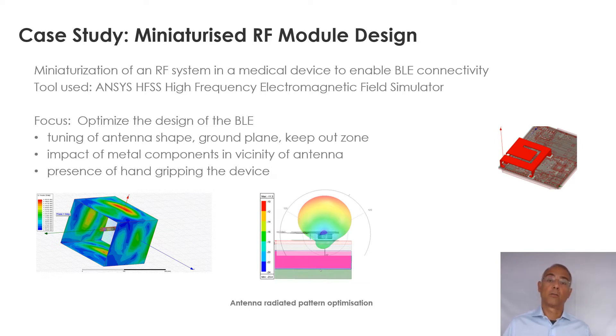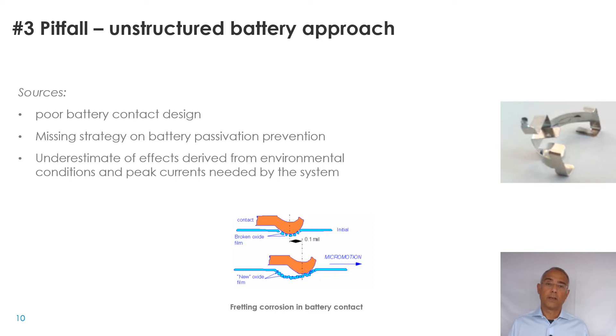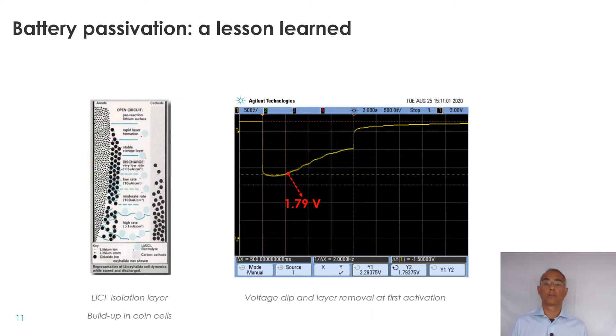You need to ensure the link to the smartphone remains reliable even in these conditions. Pitfall number three: not enough focus on the battery interface. The battery may be an off-the-shelf component, but it connects to the electronics typically via a custom battery cage. The contact itself needs to be designed properly to avoid oxide buildup that causes intermittent failures. Also, do not forget about battery passivation — an electrochemical buildup of an isolation layer that prevents discharge when the battery is not in use. With modern processors drawing very little current in deep sleep, passivation continues, so you must address this from a product strategy standpoint, planning how to wake the device after two or three years of shelf life.